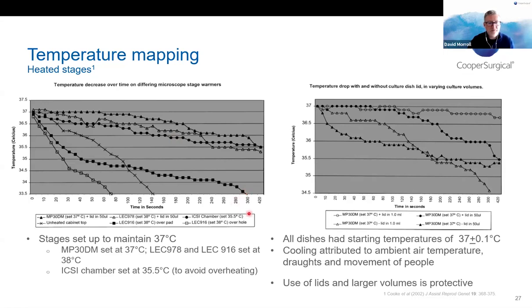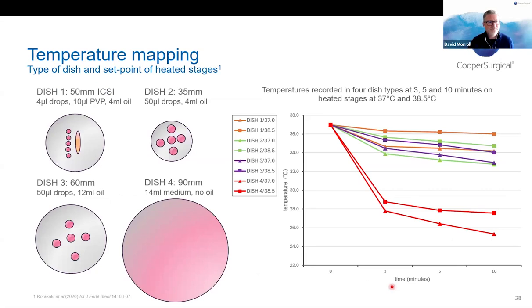And what they also stated was that if you are able to leave lids on dishes, if you're not doing manipulations, or if you can use larger volumes, those are both protective. So they slow the rate at which temperature decreases. Now, a similar, more recent study from 2020 by Kokakali and colleagues actually tested 4 different types of dishes. You can see a typical ICSI dish, small culture, large culture, and the big 90mm dishes. And what they did here is they checked temperature at 3, 5 and 10 minutes on a heated stage at 37 degrees and preset at 38.5.